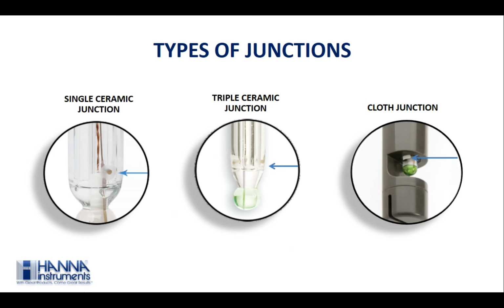Next is the cloth junction. An acceptable cloth junction is a replenishable type. When electrode response becomes sluggish and eventually impossible to calibrate, one can easily renew it by using an ordinary pair of scissors to simply pull out a small portion of fiber junction, and you will literally have a reconditioned pH electrode.